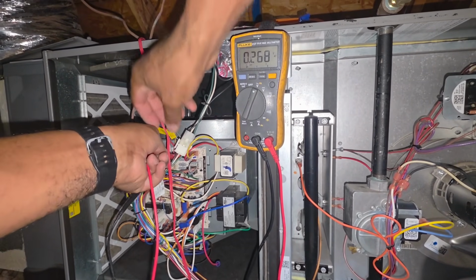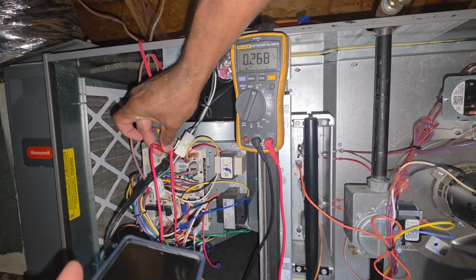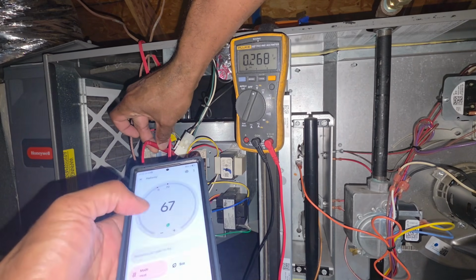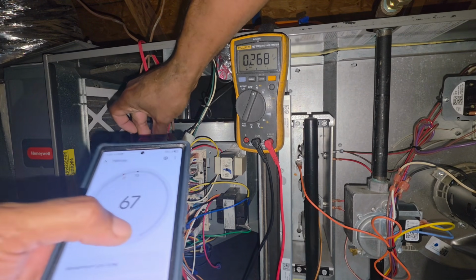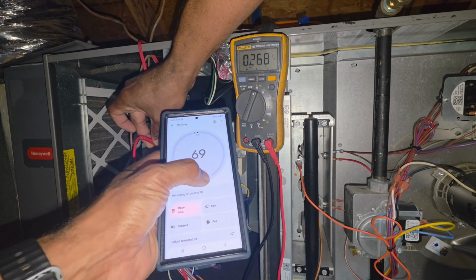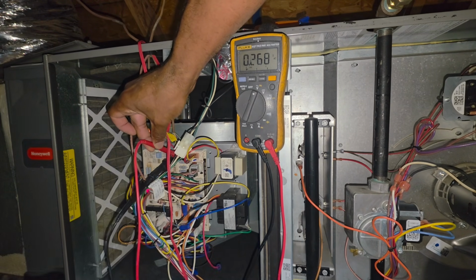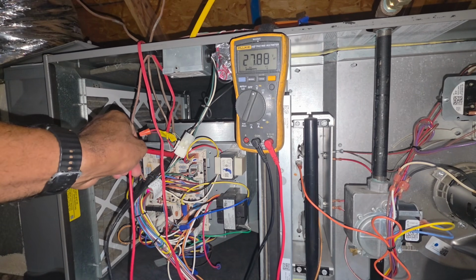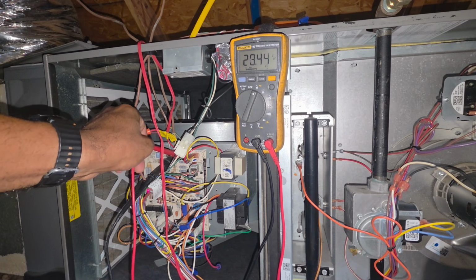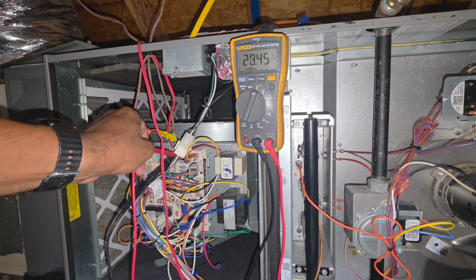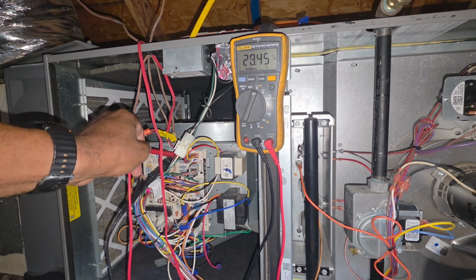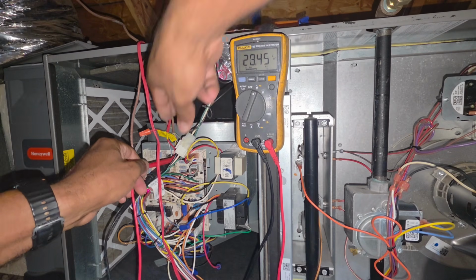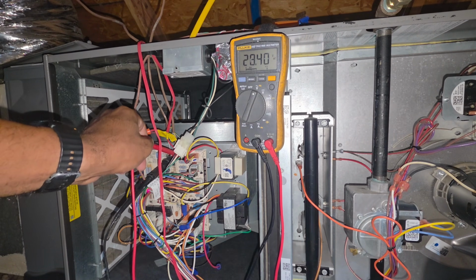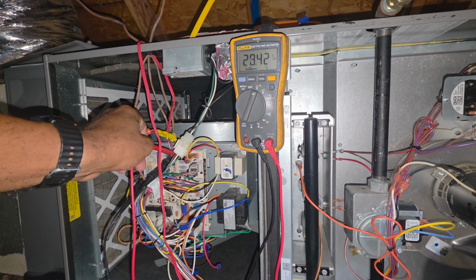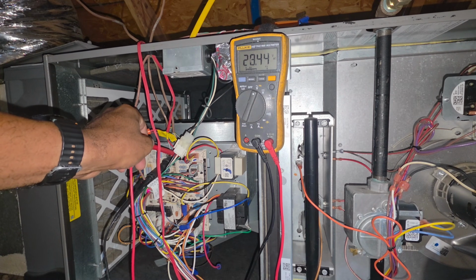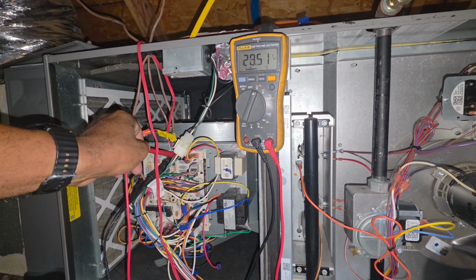I'm gonna hold this red on W1, and you're gonna see when I call for heat, we should start getting 24 volts. As soon as I call for heat, you see that change to 24 volts. That's a part of troubleshooting right there. If I call that thermostat and I call for heat, and I'm not getting 24 volts right here on my W1, if I was getting 0, we may have an issue with the thermostat because I'm not getting signal at my control board when it's called for heat. Okay?